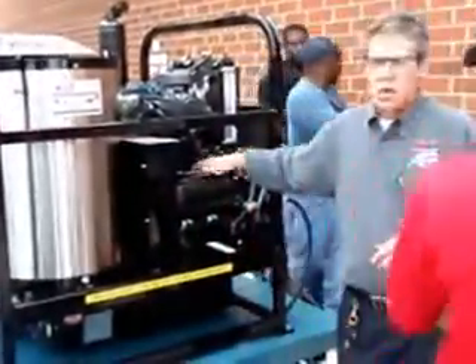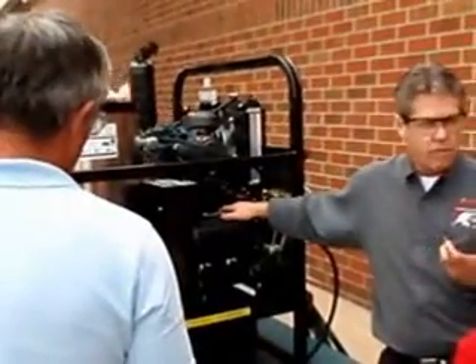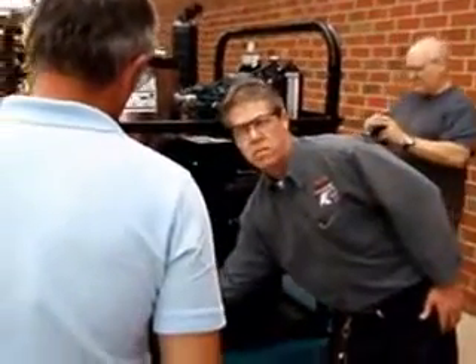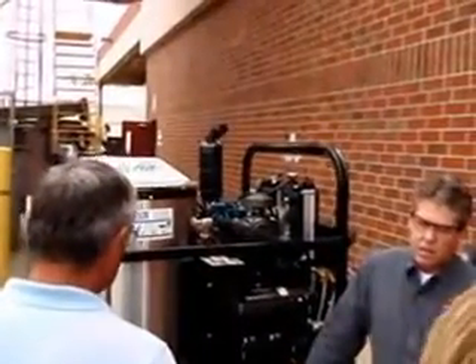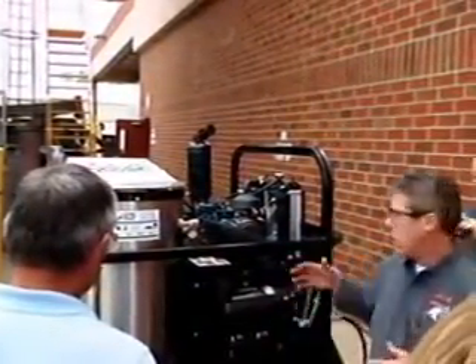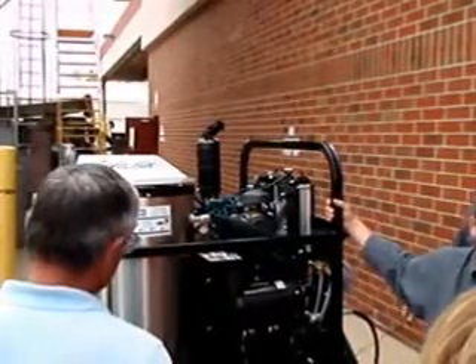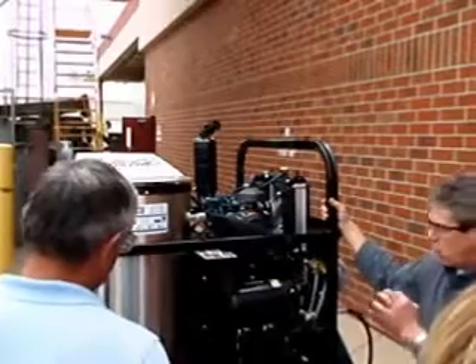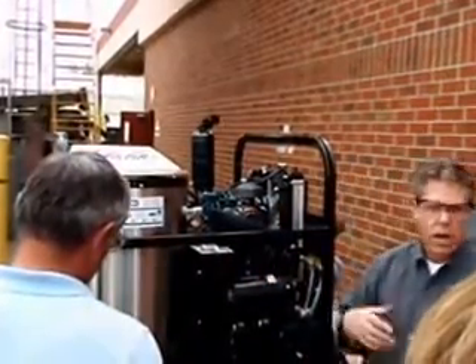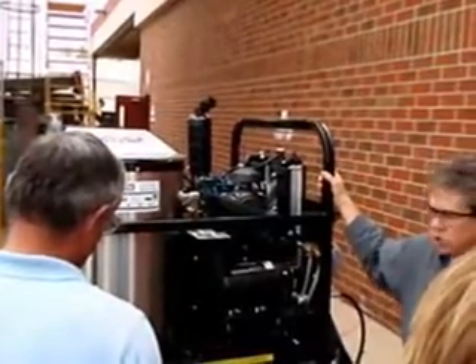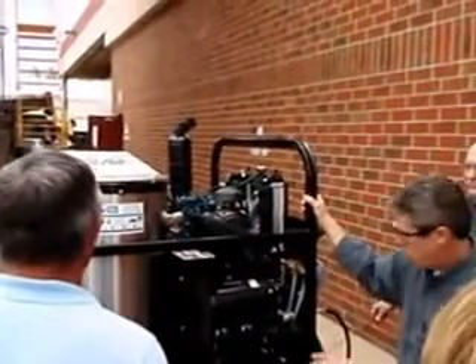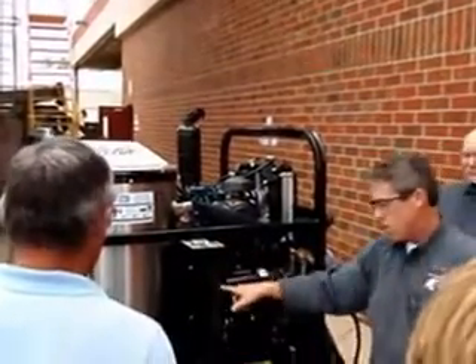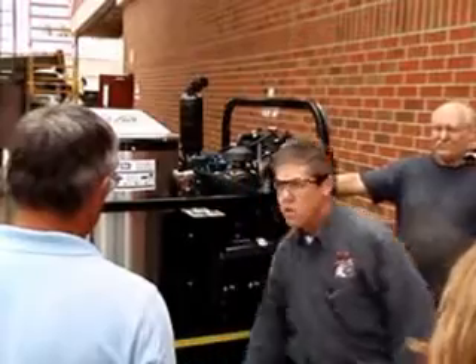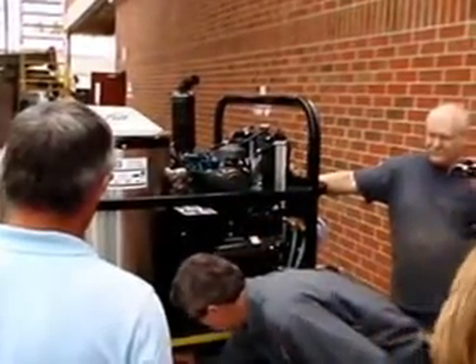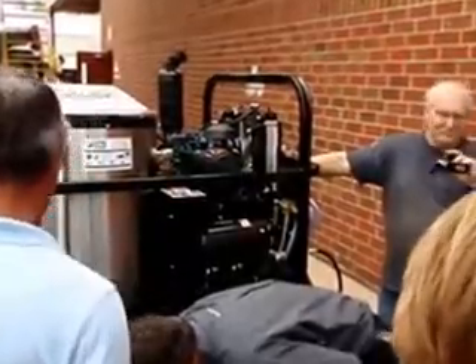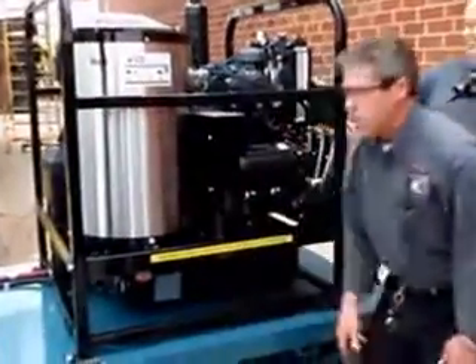This is your generator. That's providing positive 110 volts of electricity to this burner system. The diesel, the 12 volt DC systems typically operate either off of a rectifier or directly off of a battery. So if there's any low voltage situation, you're not getting enough air, and there's a whole series of potential issues that you have with the DC system. So with the 110 volt system, as long as that engine's turning, this generator's turning, this generator's pushing power to this burner system. So it's a 110 volt burner motor, and you've got your fuel pump, fuel solenoid, ignition system.